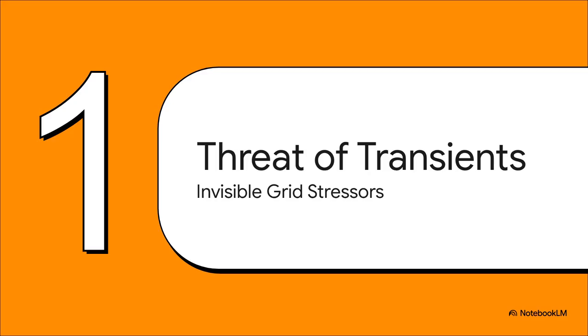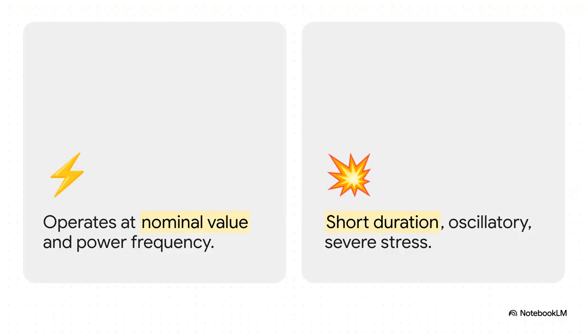Starting off with Section 1, the threat of transients, the grid's invisible stressors. It's no secret that as our grid shifts toward a decarbonized landscape, one that's heavily reliant on inverter-based resources like solar and wind, we're facing entirely new rapid stresses. Now, as engineering professionals, you are already deeply familiar with steady-state operations. Under normal conditions, our components hum along comfortably within about 10% of their nominal voltage value, right at that nominal power frequency. But a transient overvoltage, that is a completely different beast.